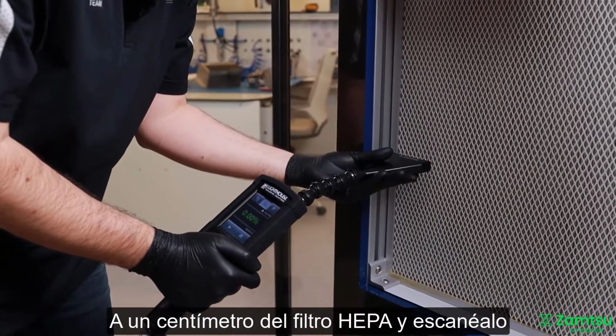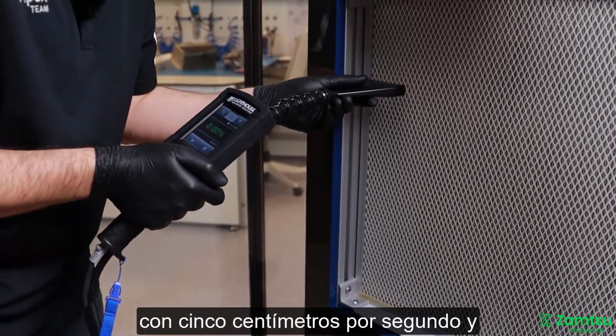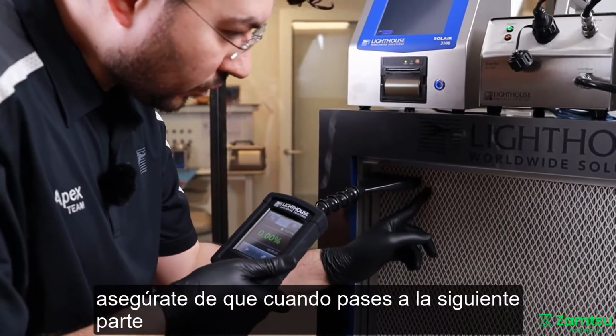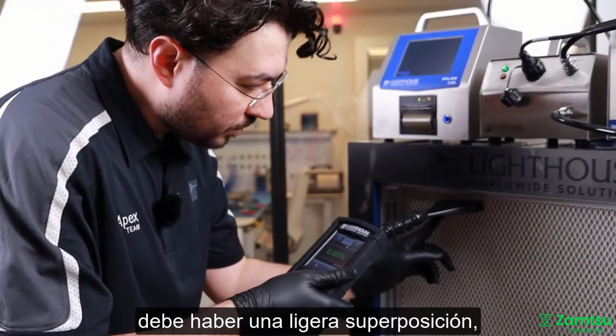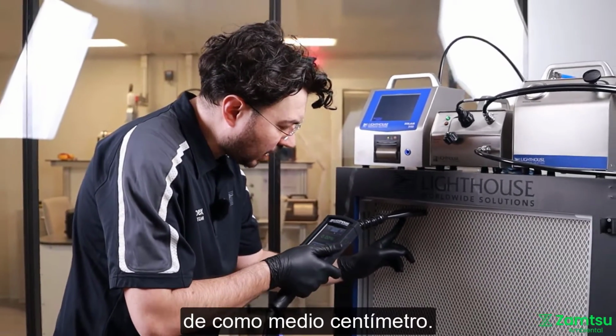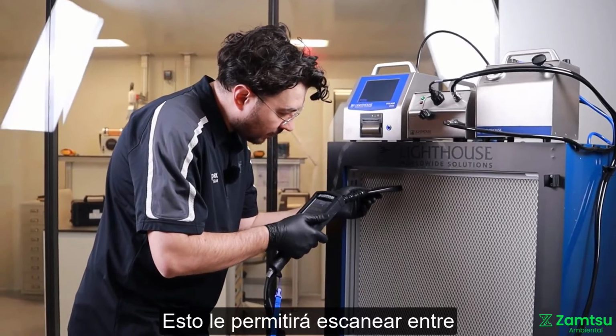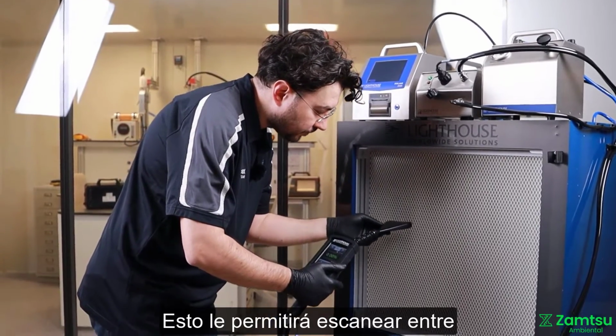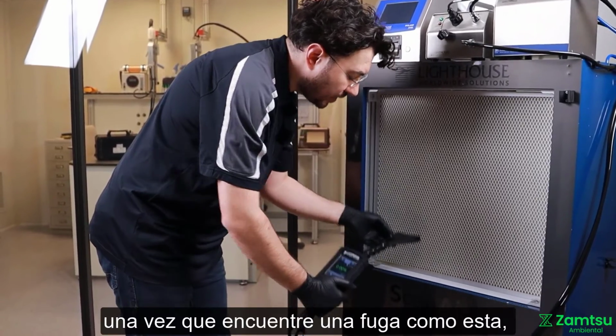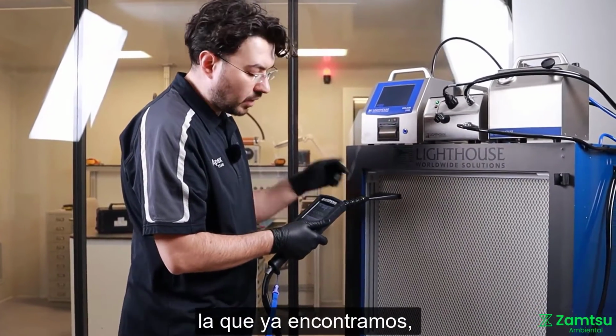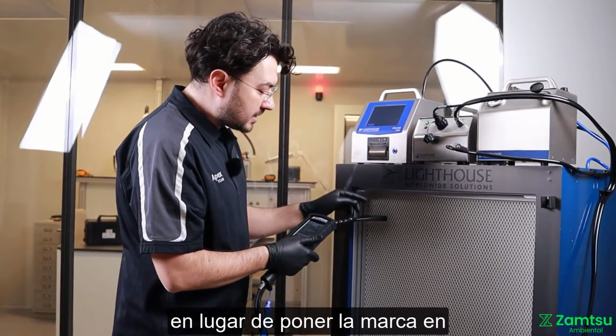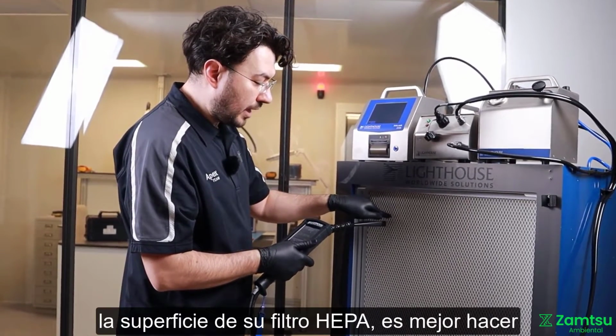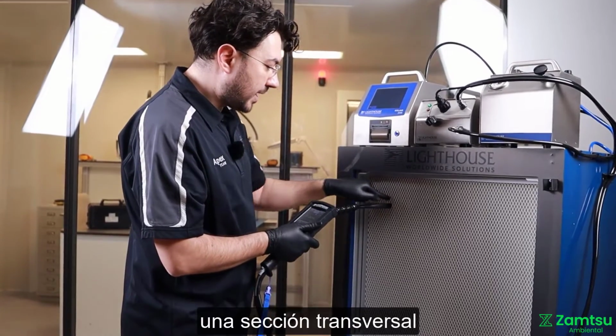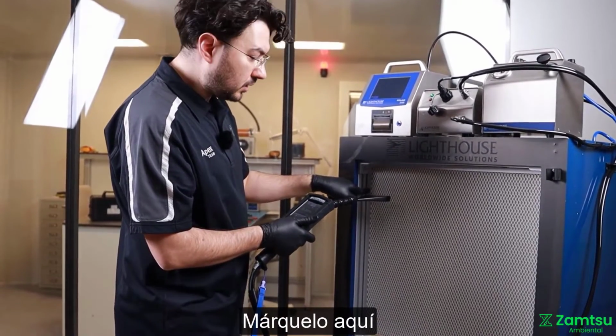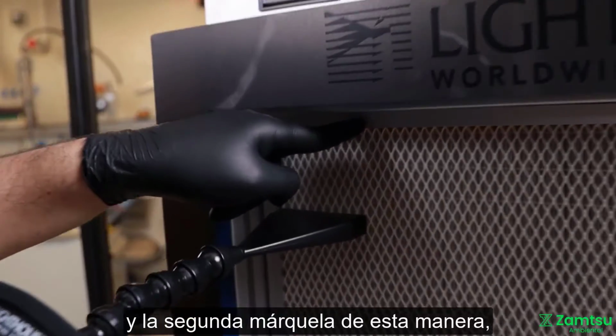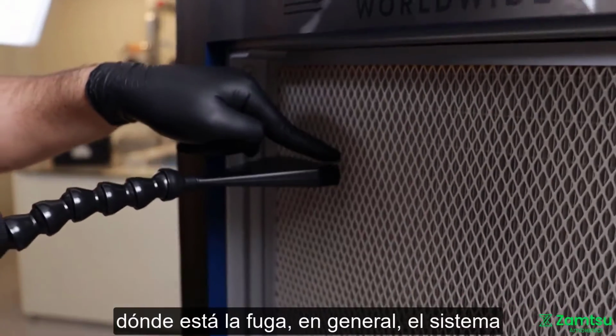Keep it 1 centimeter away from the HEPA filter and scan it at 5 centimeters per second. And make sure when you move into the next part, there should be a slight overlap, like 1 centimeter, half an inch, so that this will allow you to scan in between passes. And once you find any leakage like this, the one we found already, instead of putting the mark onto your HEPA filter surface, it's better to make a cross section, mark it here, and the second one mark it this way, so that the cross section will tell you where the leak is.